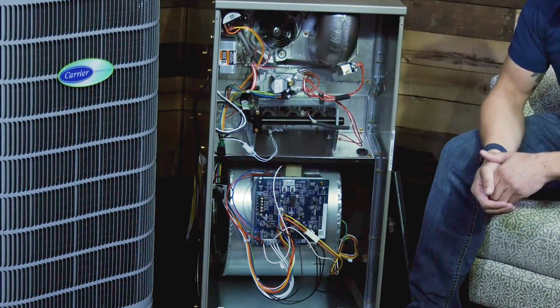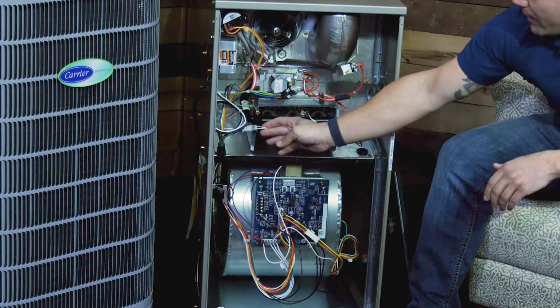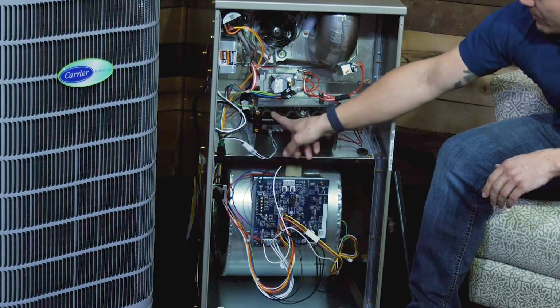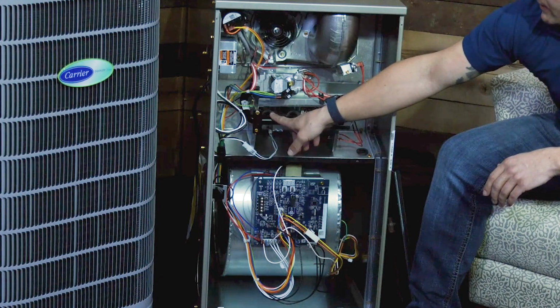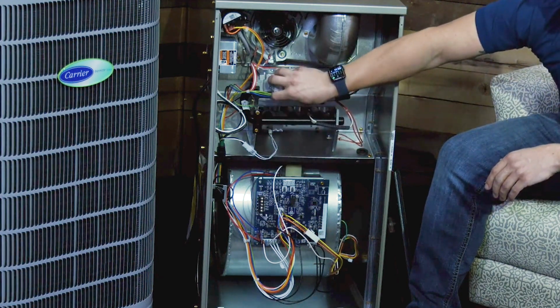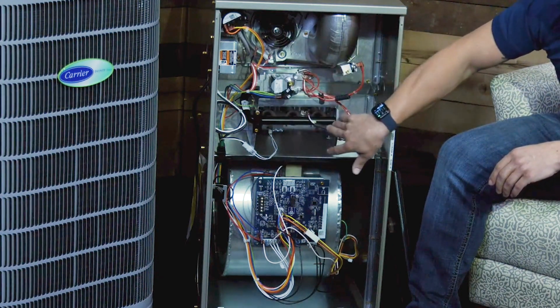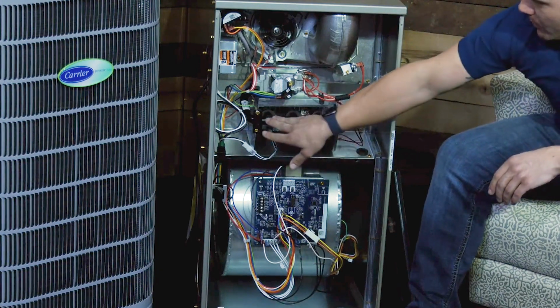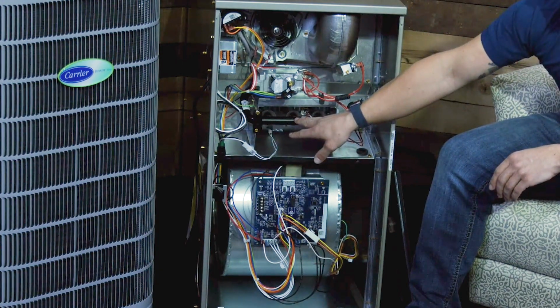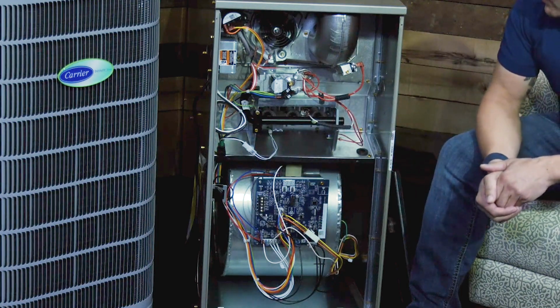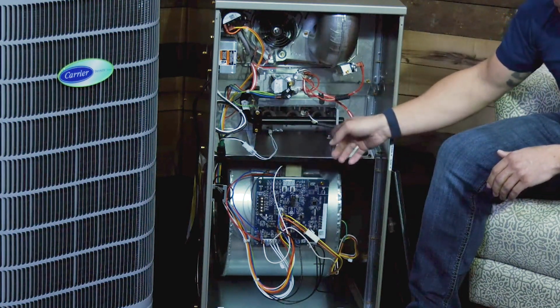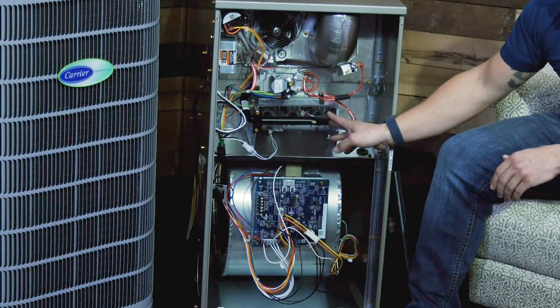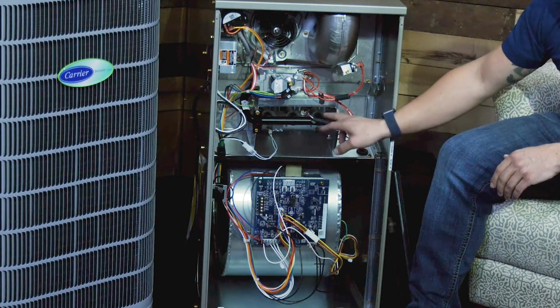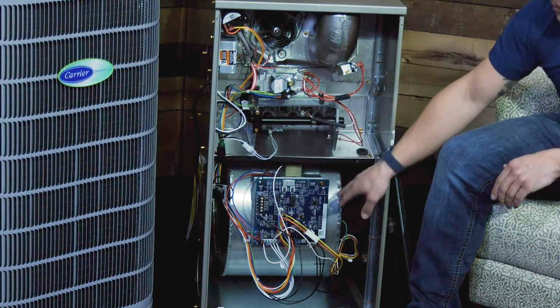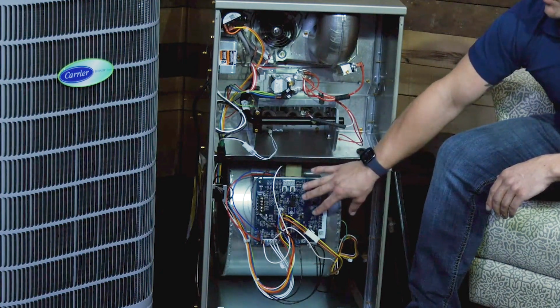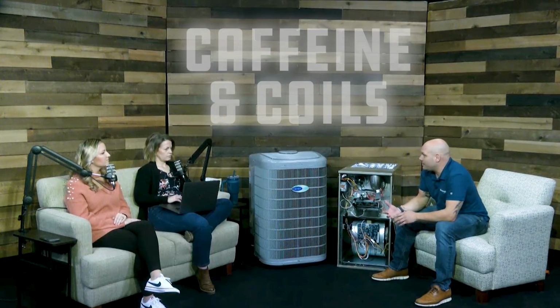Step 3 is going to be the igniter, and that's this wire right here. After your igniter turns on, it'll go to the gas valve. It'll send gas through the burners, or through your bar right here, and then it'll actually ignite. After the gas flows through and ignites, you have this wire right here, which is called the flame proving switch. Once the flame proving switch sends a signal to the board, then your blower motor will turn on. So I know that was quick.